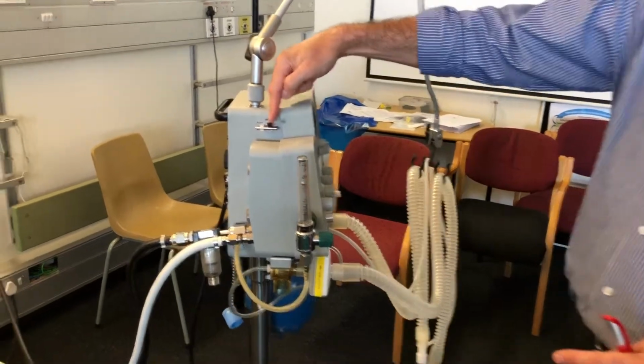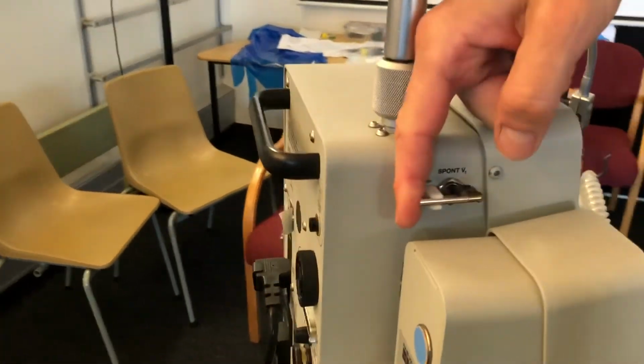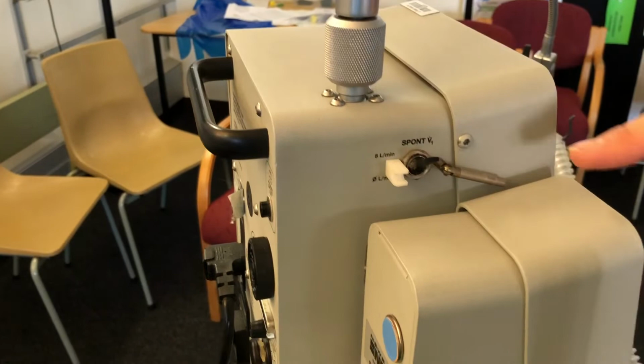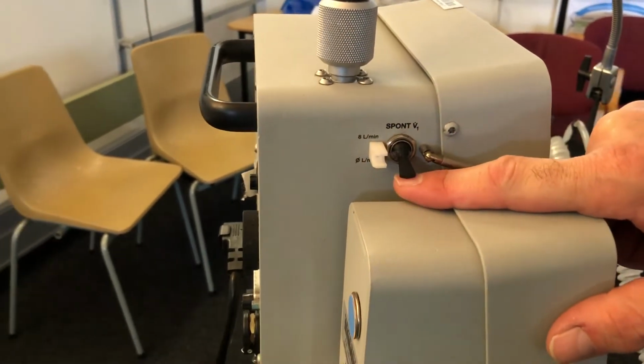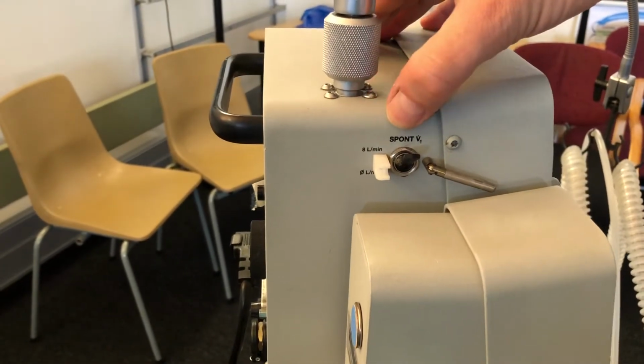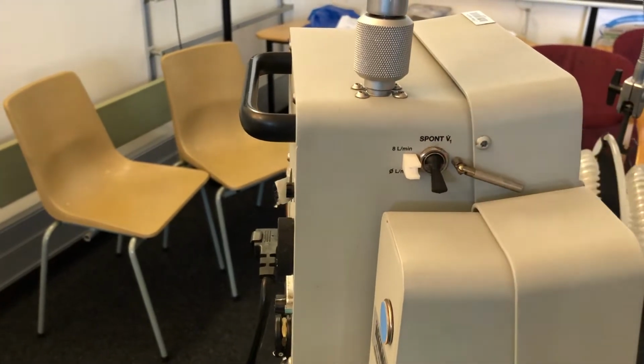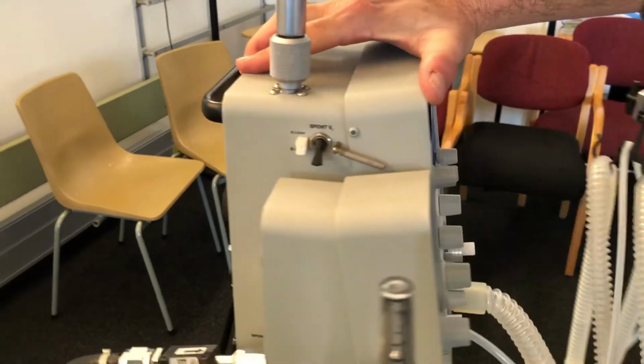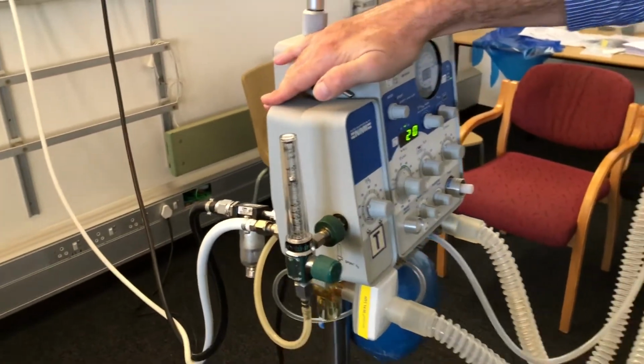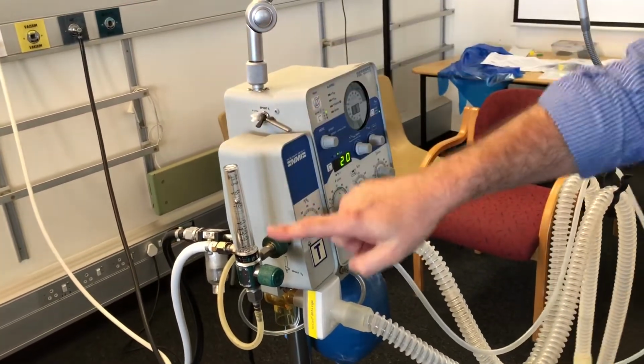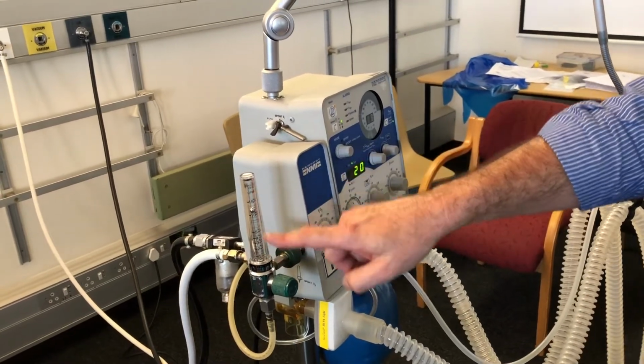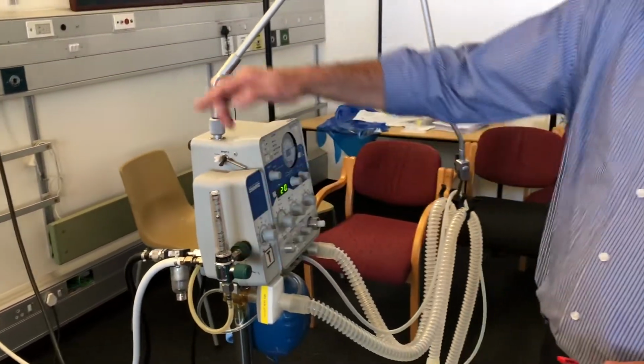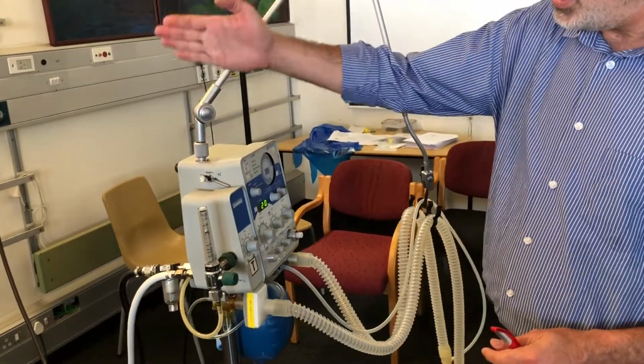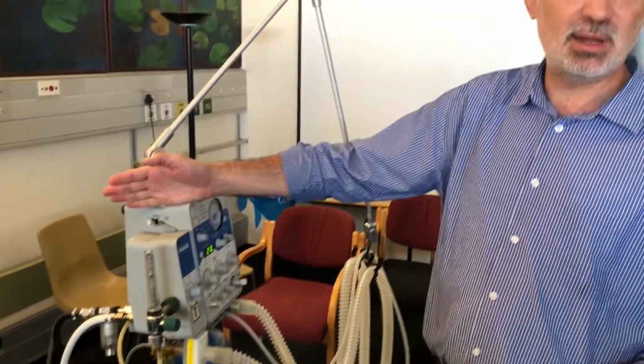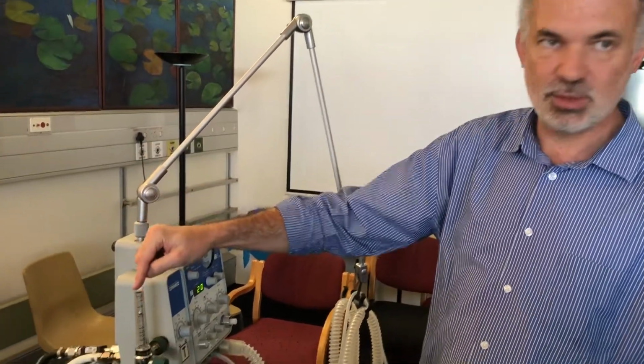The second source we have is governed by this little switch. So if I open the gate here, I can then switch the switch up and down. If I switch it up, it says 8 liters a minute. If I switch it down, it's off. So if the switch is switched down, then there's no gas flow for spontaneous breathing from here, and all of the flow for spontaneous breathing is from the rotameter. If I switch this up, then the machine's delivering 8 liters per minute as a preset, plus whatever I've dialed in the rotameter.